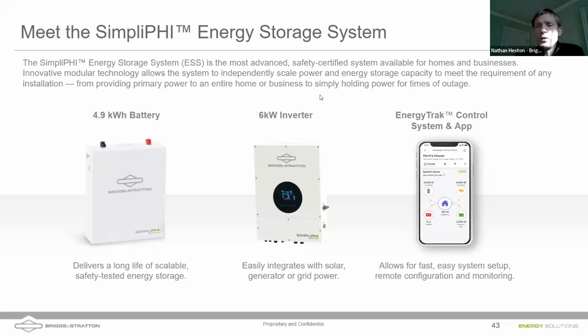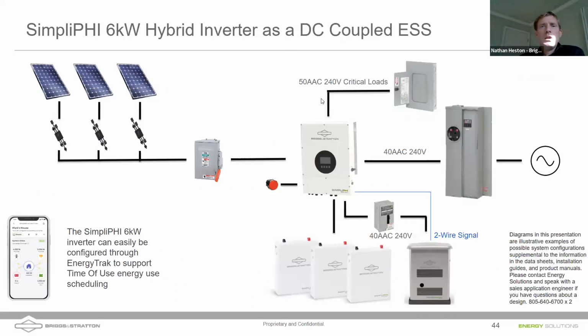You've got a customer that wants to do something different with their system, or maybe wants to increase the amount of battery reserve they're having due to inclement weather. You can do that from the office instead of having to go out and make a change on the physical system. So here's an example of a DC coupled Briggs & Stratton ESS. I am showing it here with a generator. Of course, that's optional. It's not necessary, but it's got that 2-wire start signal with a generator. DC coupled, that solar array is just passing through Keep Alive rapid shutdown devices. Those are APsmart there. You've got the disconnect, you've got the rapid shutdown button. So it's a nice example of a DC coupled ESS. Of course, you can parallel more inverters than just one.